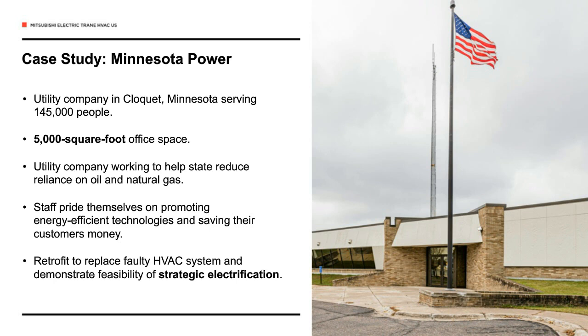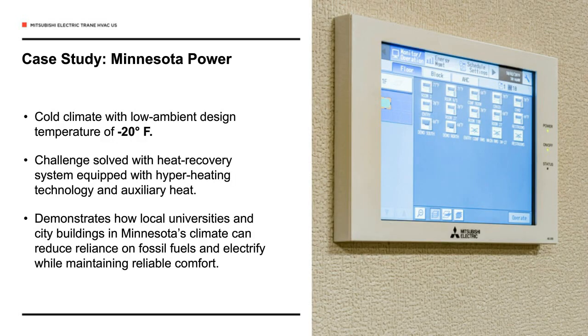As I mentioned on the last slide, this is a very cold climate area with a low ambient design temperature of -20 degrees Fahrenheit. Based on 30-year averages, design temperatures only occur during 1% of all hours in a year. This challenge was solved with a heat recovery system equipped with hyper heating technology and auxiliary heat. Minnesota Power is now an example of a highly efficient, sustainable heating and cooling facility in its state.